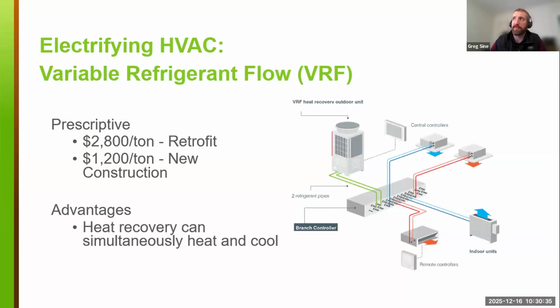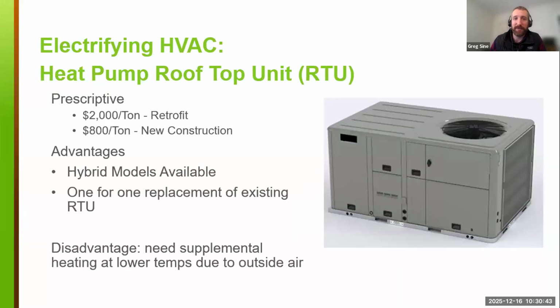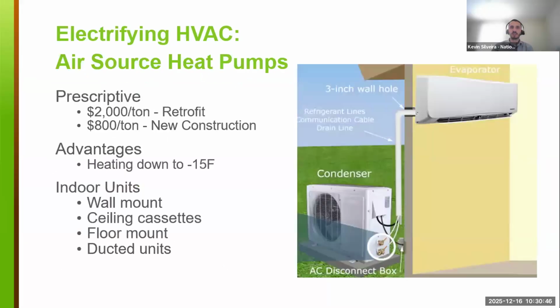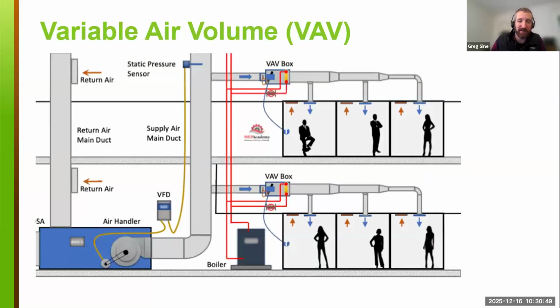Just like the VAV situation, it's important to note, actually, can we go back to that slide, the VAV one? So you can see here, Kevin had touched on it, most of the heating is actually being done by the boiler in this type of scenario, even if the RTU or air handling units are replaced with a heat pump section, so there'd be less gas savings. So for example, if we're doing a CBA here, we'd look at how we adjust both the air handler, the RTU, as well as the boiler serving those VAV boxes. So that's what we'd look at in a CBA.